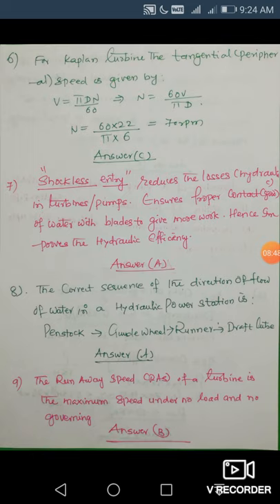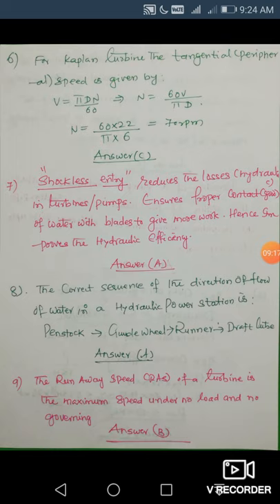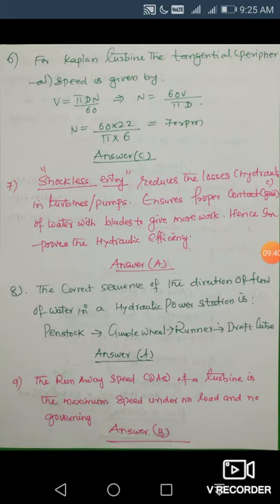Next question: the runaway speed of a turbine is the maximum speed under no load and no governing. Governing refers to controlling the turbine speed according to load — demand is higher in the daytime and lower at night, and speed is adjusted accordingly. When there is no load change and no governing, the speed will be maximum. The key terms are no load and no governing. Your answer is B.